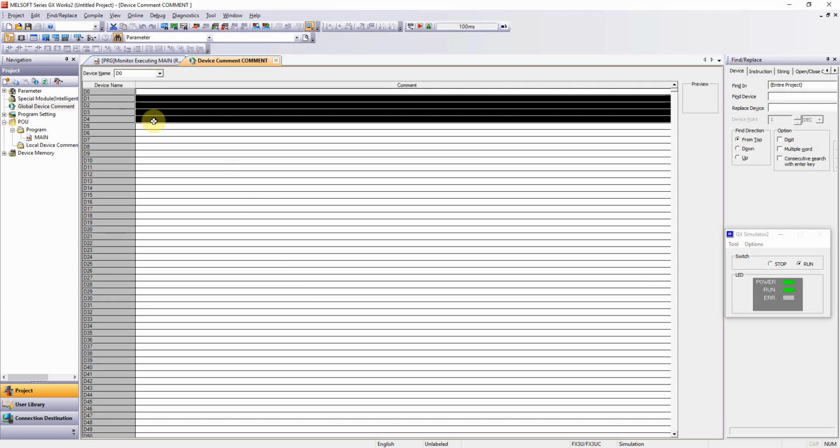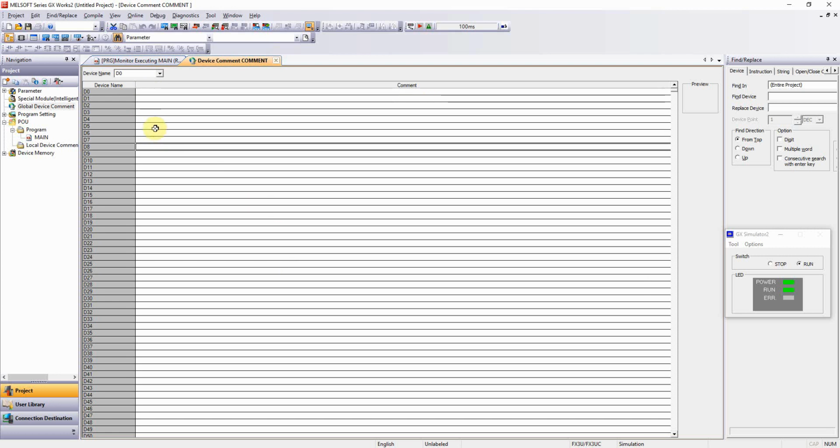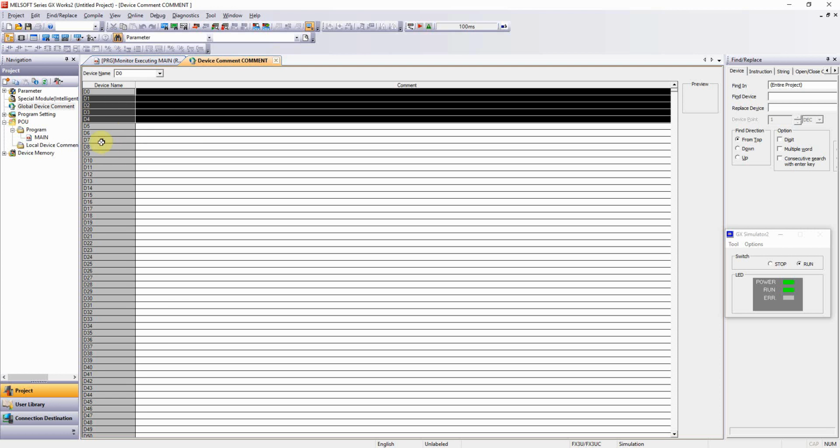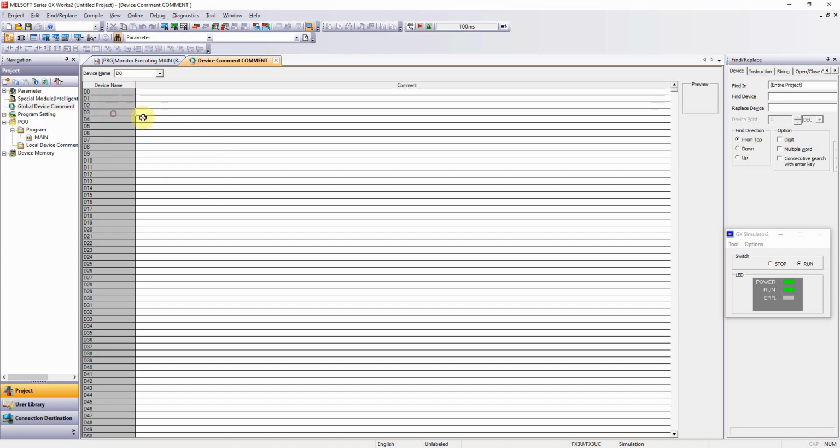That's all kind of one of the tricks to Mitsubishi programming. So you kind of have to keep track of that stuff on your own. It's not going to group your addresses together when you reference D0 and it's using up 4 variables. If you say D3 plus 1, it's still going to do that math somewhere else, and you could potentially be using these 64 bits or whatever it is, and still be accessing D3 somewhere else or D4 somewhere else, and it's going to screw your numbers up, and you're going to be very confused.